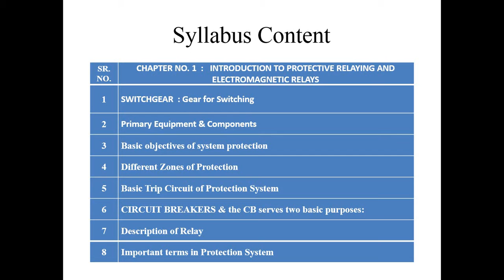Okay, switch gear and gear for switching. Here switch gear is divided into switching device, control and sensing device, and decision making devices. Switching devices are circuit breakers, isolators, switches, relay, etc. Control and sensing devices are current transformer (CT), voltage transformer (PT), reactors, tripping units. And decision making devices are protective relays, lightning arresters, fuses, etc.